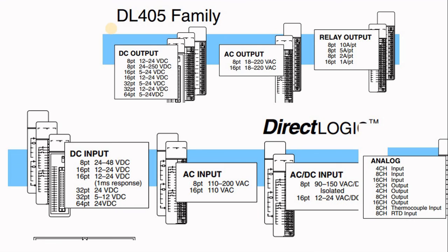There is Productivity. DeltaV is different than Honeywell, different than Yokogawa, and so on. So please go into each one of those cards and look at exactly if it is an isolated output, if it is not, what is the power supply, where the power supply comes from, and so on. What is the analog output minimum and maximum resistance, digital output rating, and voltage, and so on.